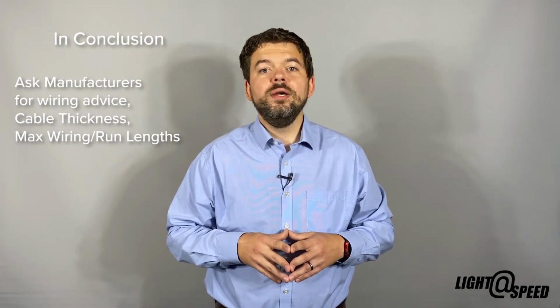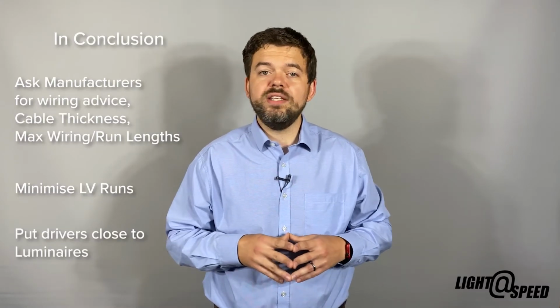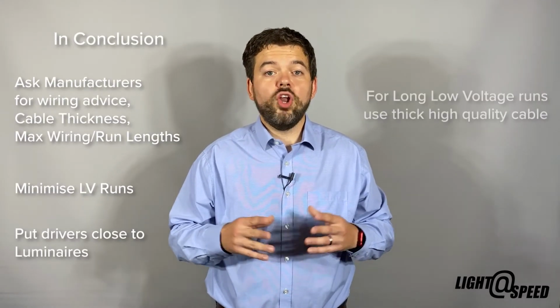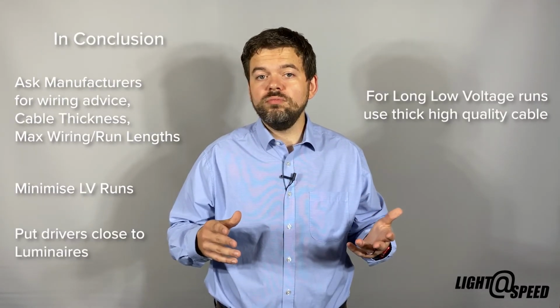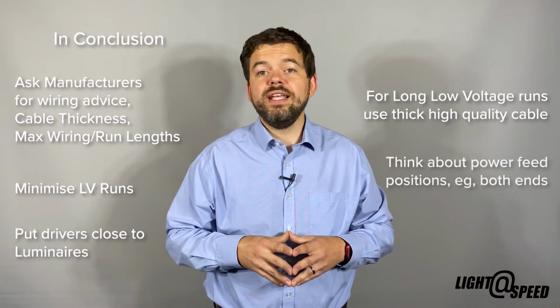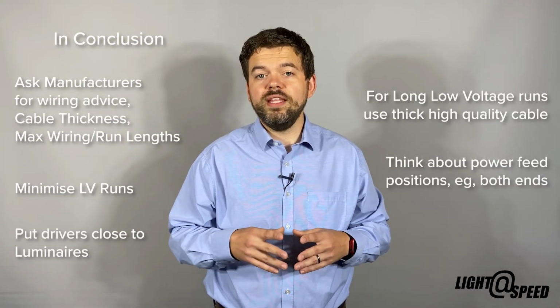In conclusion then, always ask manufacturers for their advice, suggested cable thicknesses and max single run lengths. Minimize excessive low voltage cable runs and keep drivers as close to LED sources as you can. If long low voltage cable runs are unavoidable, use thick high quality cable and consider feeding the LED system from both ends.